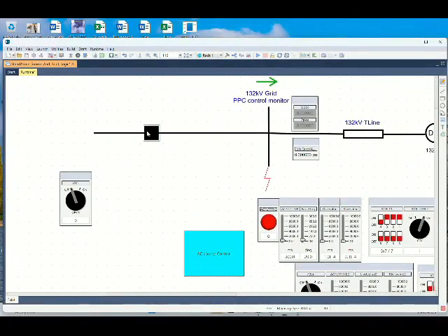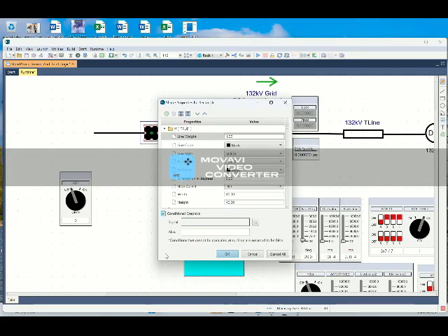Okay, and I want to show you that we can draw an active mimic. So now you can basically go properties, and then conditional graphics. You tick that box, and you've got to select a signal. So from runtime, controls, variables, and then it'll be under inputs. It would normally be under variables, but it's directly tied to an input, so it's not independent of the switch.